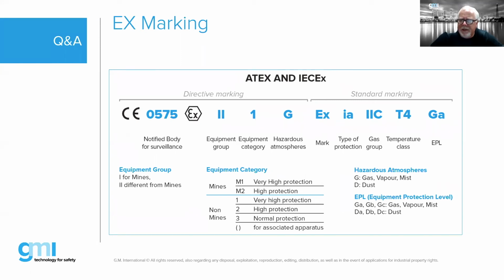Well, actually, EXNA is non-arcing. It's a protection concept that's referenced in 60079-15, and EXIA is intrinsic safety suitable for zone 0. So EXNA, all the N-type concepts, are protection concepts that are only suitable for zone 2, where EXIA is suitable for zone 0, 1, and 2. Yeah, so there's a big difference between the two. There is. Okay, why don't you go through a little bit about this marking? Sure. I'll go through this real quick.